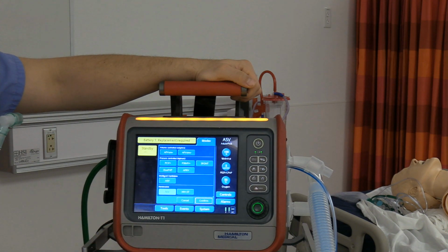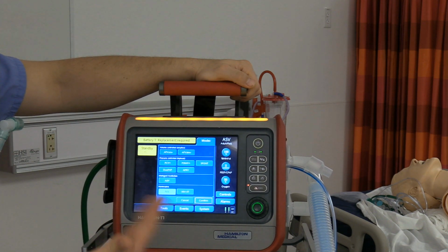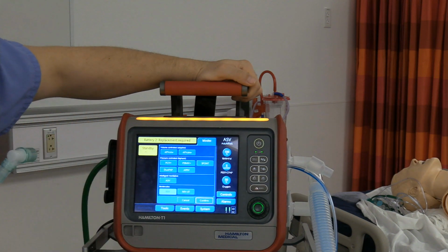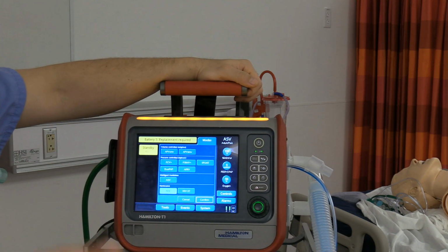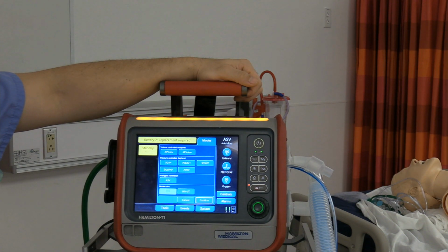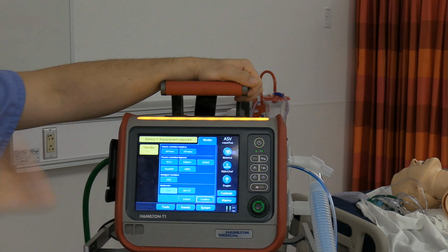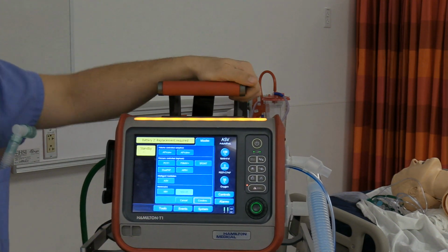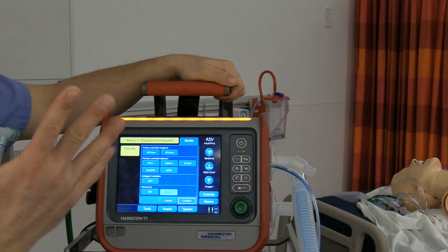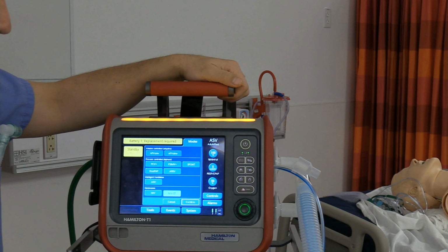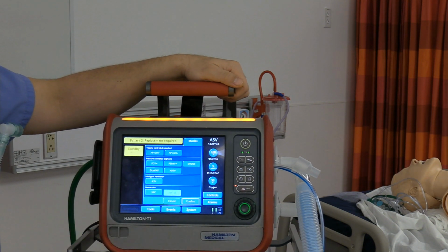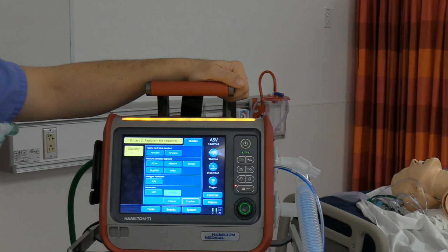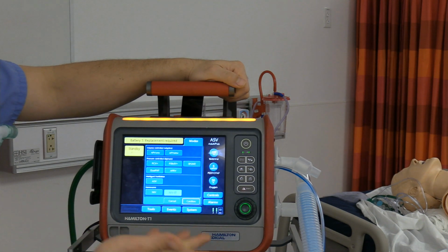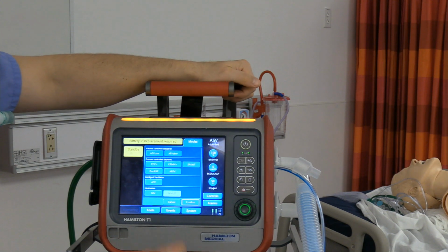So I've got typical non-invasive with no backup rate. It does have an apnea alarm, which you set for 20 seconds, so you do have backup ventilation, but it's not setting time-triggered breaths to fall back upon if they don't trigger for a moment. What you're typically used to, if you're working with the V60 or some of the other non-invasive units out there, is non-invasive ST. So you've got pressure support for your patient, a baseline pressure, pressure support, and a backup rate. If you have a different software option, you might have high flow nasal oxygen through this, and that would be a heated wire system here.